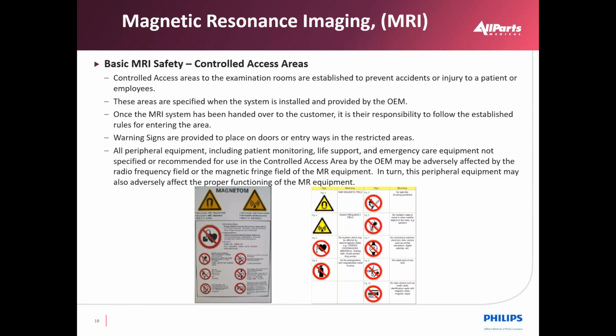Be aware of the different controlled access areas. There are restricted access warning signs at the doors and entrances to these areas. The customer will be aware of what can and cannot go into the scan room area. As previously mentioned, if you're going to be working on the MRI, ensure that you have tools that are allowed to go into the scan room safely, such as titanium hand tools or similarly non-ferrous tools.